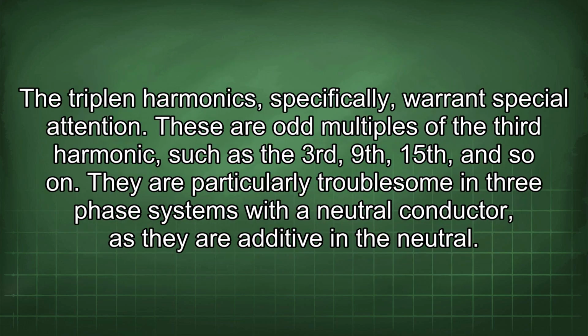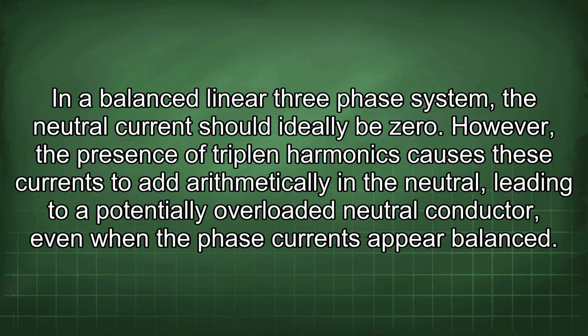The triplen harmonics specifically warrant special attention. These are odd multiples of the 3rd harmonic, such as the 3rd, 9th, 15th, and so on. They are particularly troublesome in three-phase systems with a neutral conductor, as they are additive in the neutral. In a balanced linear three-phase system, the neutral current should ideally be zero. However, the presence of triplen harmonics causes these currents to add arithmetically in the neutral, leading to a potentially overloaded neutral conductor, even when the phase currents appear balanced.